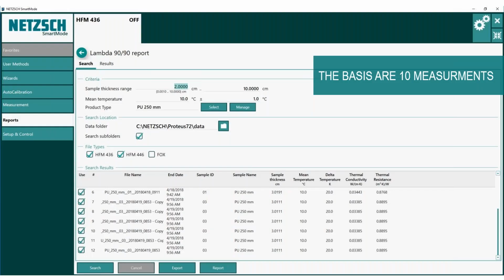So what we do in our software, we added the so-called Lambda 90/90 report directly in the measurement software. You can search for some criteria: sample thickness range, mean temperature, product type. What product type means, I can explain a little bit later. You can search in a dedicated location, and you can search for different file types. The HFM 436 and 446 are both NETZSCH instruments, and you see also a check mark, which is called Fox. I'm pretty sure some of you know this instrument from your quality control. This is a machine from one of our competitors, and we were asked by our customers to include the measurements from different machines into our reporting system.